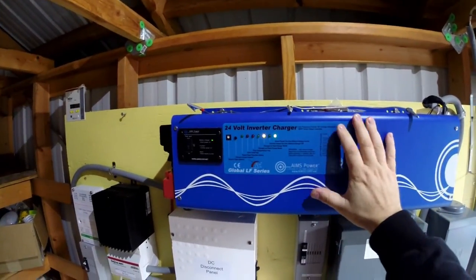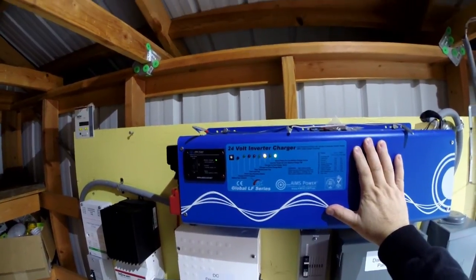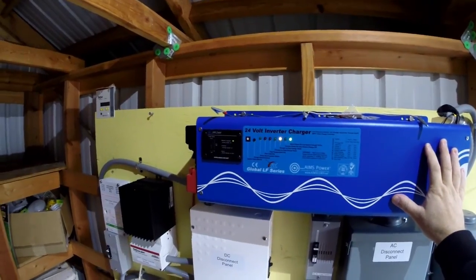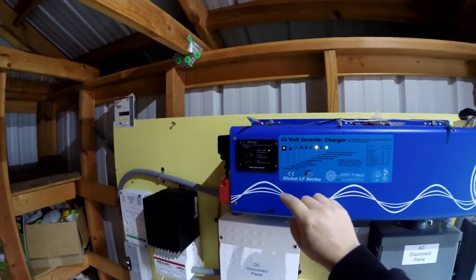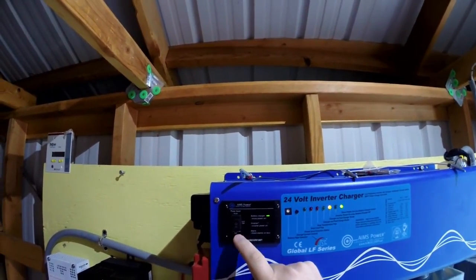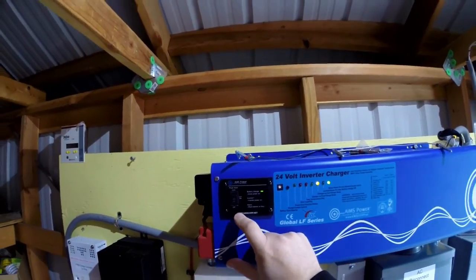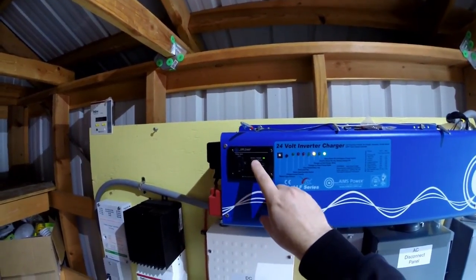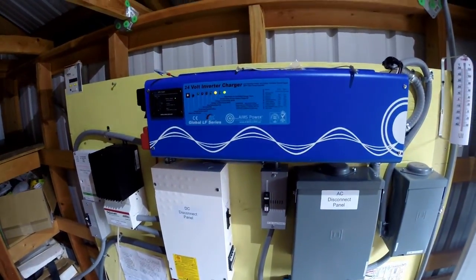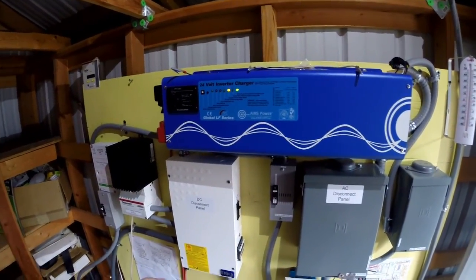I have a 4000 watt pure sine low frequency inverter, 24 volt from AIMS Power. It's an industrial grade inverter and it's got a few modes on here. It's got a power saver mode if you want to use it as a backup system, an on-all-the-time mode, and off of course. In power save mode, it'll basically go into sleep mode until you pull 25 watts or more, and then it'll turn itself on and power whatever you need.